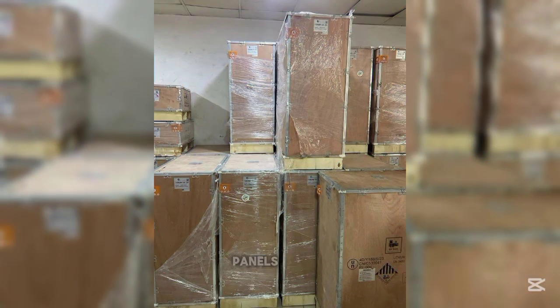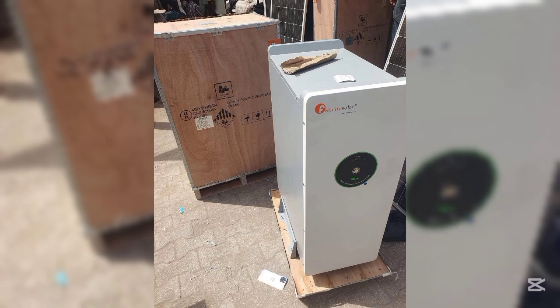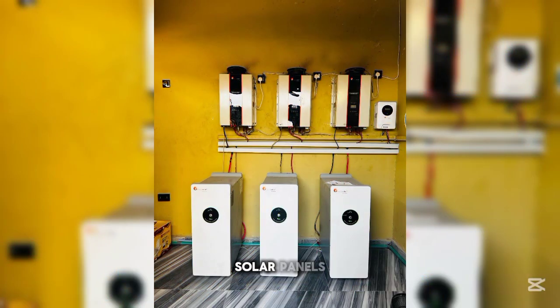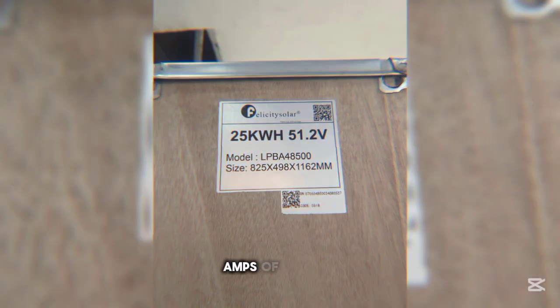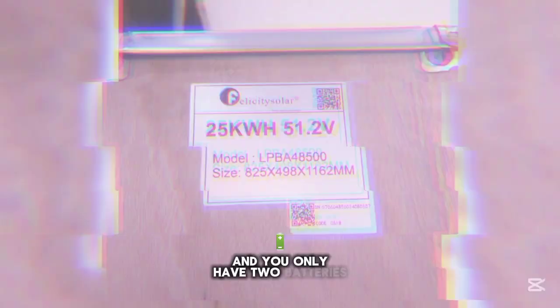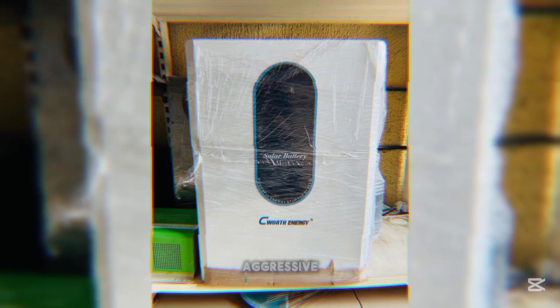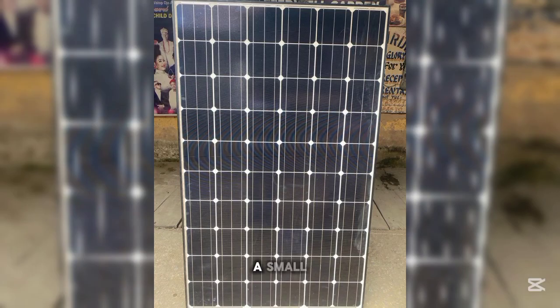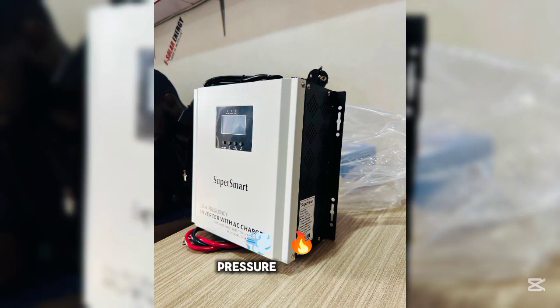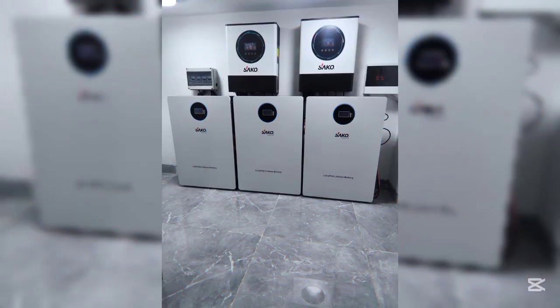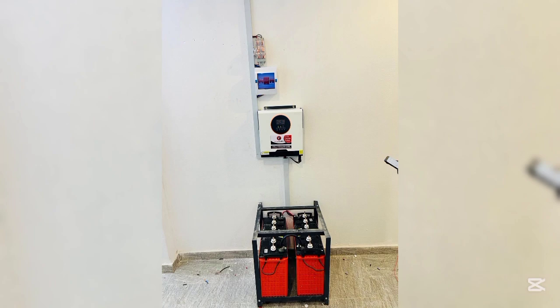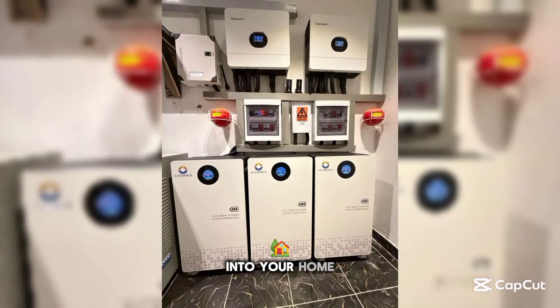Number 4, the charging current overload. Your solar panels on the roof don't care how many batteries you have. If you have 6 massive solar panels producing 60 amps of current and you only have 2 batteries, that charge is too aggressive. It's like trying to fill a small balloon with a high pressure fire hose. The balloon will pop. Overcharging a small battery bank leads to outgassing, where your battery releases toxic, inflammable hydrogen gas into your home.